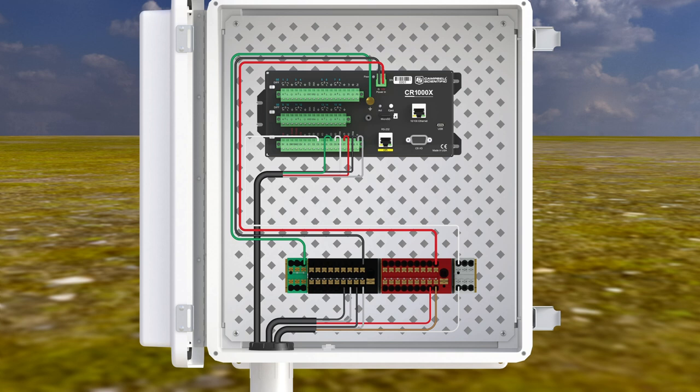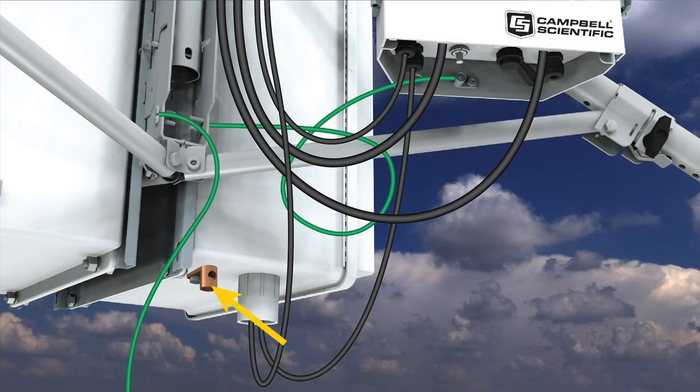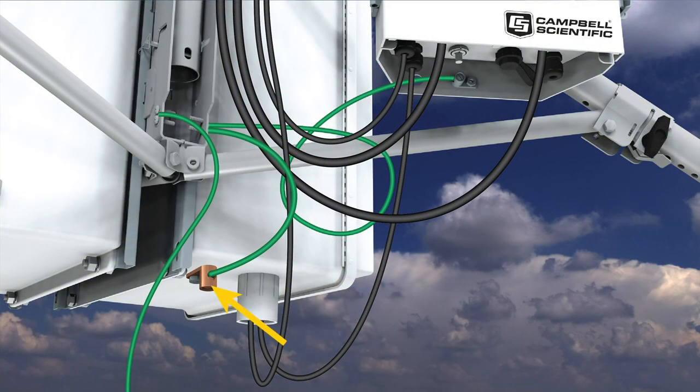Route the HygroVue 10 cable into the data logger enclosure and connect it to the SDI-12 power distribution terminal block. Connect the brown power wire to the red terminal block, the white SDI-12 data wire to the gray terminal block, and the black and clear wires to the black terminal block. Connect the internal enclosure earth ground wire to the green terminal block on the SDI-12 power distribution terminal block. Connect the main enclosure to earth ground using the ground lug on the bottom of the enclosure, then connect the other end of the ground wire to the CM110 base.